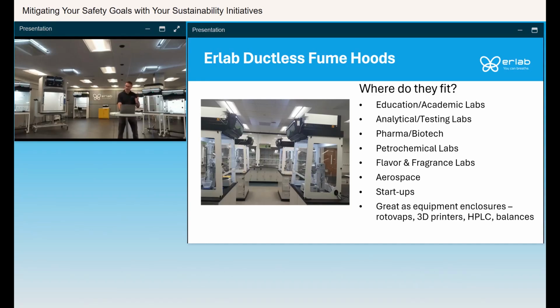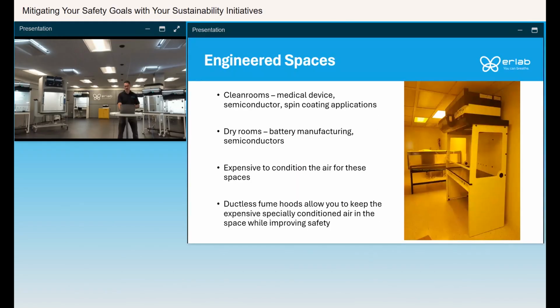So the other place to think about is if you have any specialty engineered spaces. I touched on clean rooms earlier, but with clean rooms, you have 20 to 30 air changes coming into the space through HEPA filters. You don't want to put a ducted fume hood in there because clean rooms are supposed to be positive pressure to keep the particles out. It's hard to put a ducted fume hood in there. So a lot of cases, you'll see people using chemicals in the open in a clean room without protection. Having the ductless fume hood with the HEPA filters on top, you keep the particle count integrity of the clean room, and you keep that clean conditioned air in there.